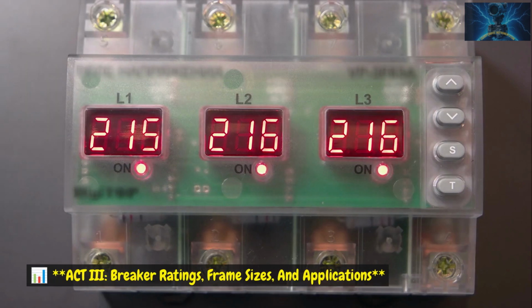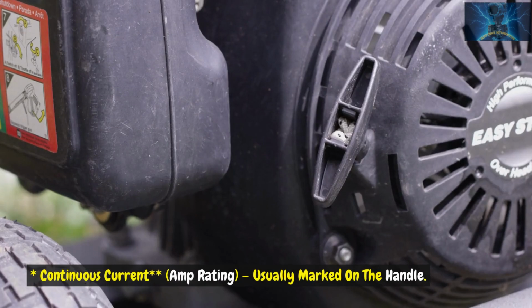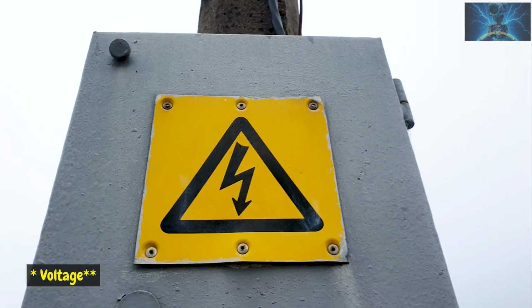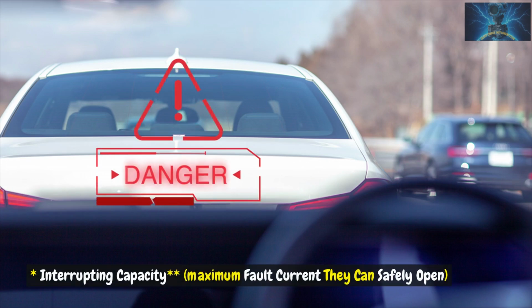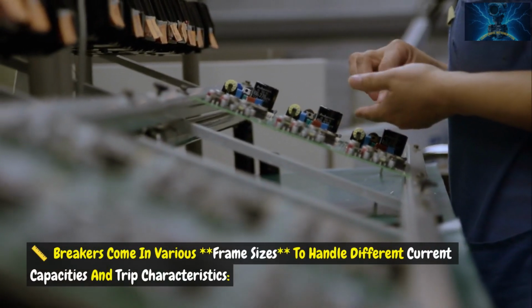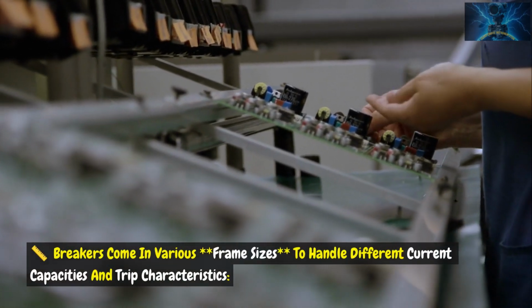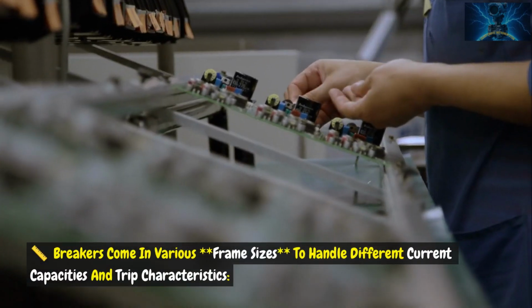Act 3. Breaker ratings, frame sizes, and applications. Breakers are rated for continuous current, the amp rating, usually marked on the handle, voltage, and interrupting capacity, the maximum fault current they can safely open. Breakers come in various frame sizes to handle different current capacities and trip characteristics.